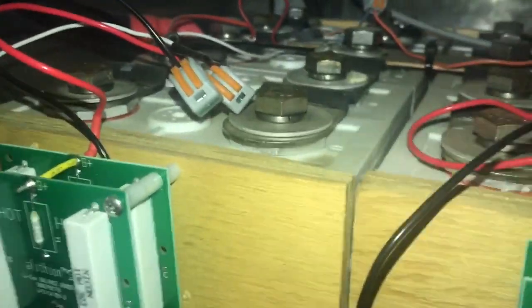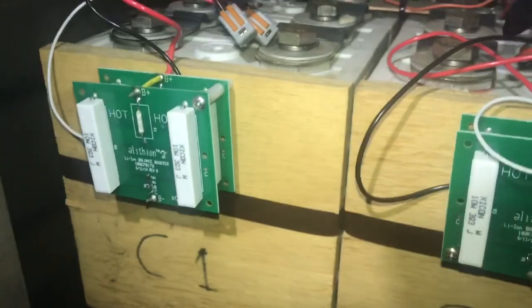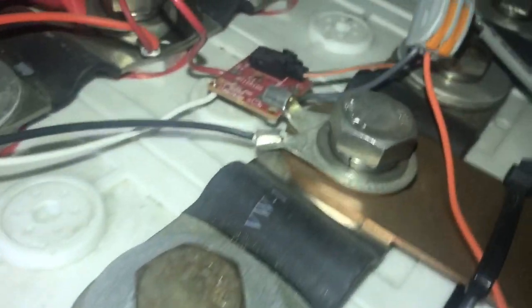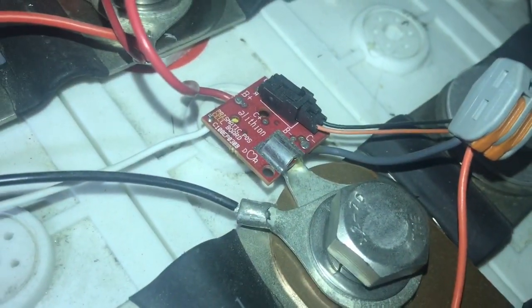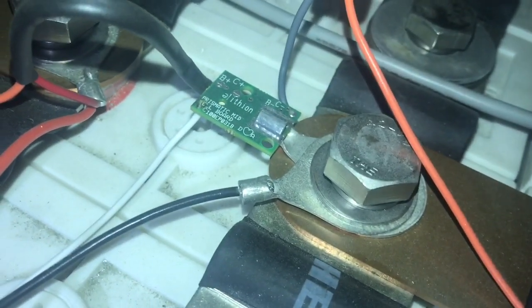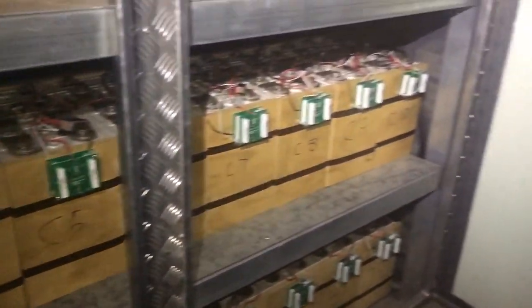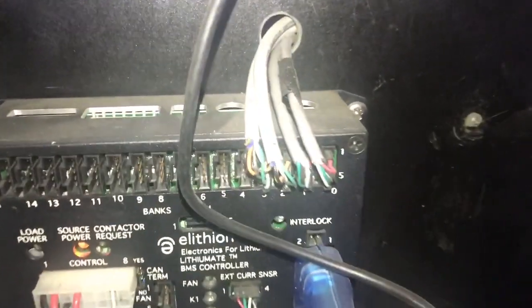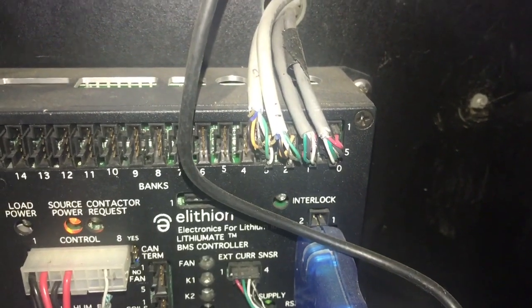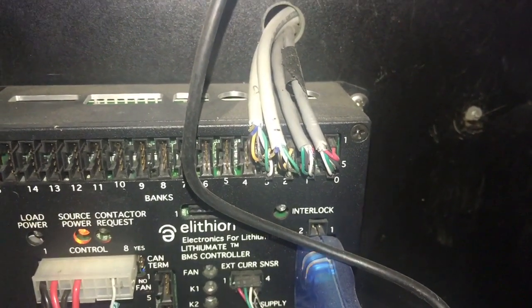It's using a lithium-ion BMS. If I come closer, this is a cell board - you can see one is red and one is green. Each of these shelves is considered one bank by the BMS. Coming back to the BMS, you can see 4 cables coming in - that's 4 banks, each one being one of the shelves coming through.